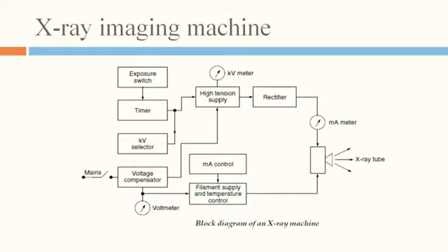A preferred method of providing high voltage DC to the anode of the X-ray tube is the use of a bridge rectifier using four valve tubes or solid state rectifiers. This results in a much more efficient system than half wave or self-rectification methods. So this is how our X-ray machine works. I hope this concept is clear.